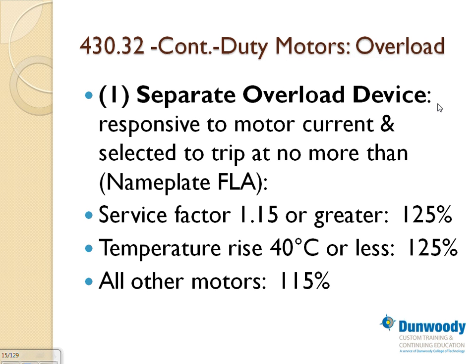15% or greater. If your motor's temperature rise is 40 or less, if it's by design, it's designed so that the temperature rise doesn't increase more than 40 degrees plus the surrounding ambient temperature, meaning it's not going to heat up by design, then the same thing, you can overload 125%. All other motors, that's not any of these, then you can only allow 115%.